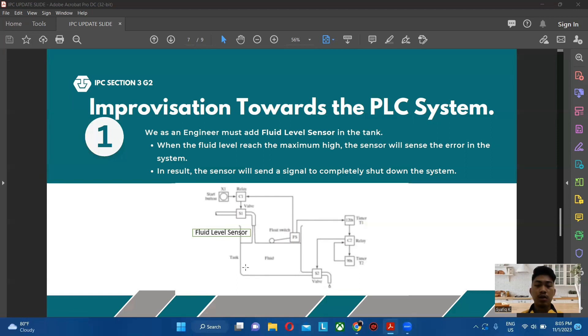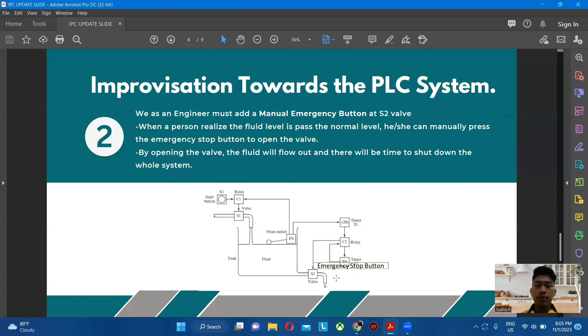This will make sure that the tank does not overflow or explode. The second suggestion is to put a manual emergency stop button at the S2 valve. In the same situation, when the fluid switch has a problem and the S1 valve is still running, the fluid will reach the maximum level. To prevent this, workers can stop the process manually by pressing the emergency stop button, which will open the S2 valve so that the fluid will flow out from the tank. From that, we can shut down the system and continue with the maintenance process.